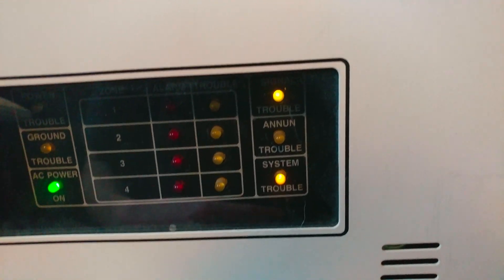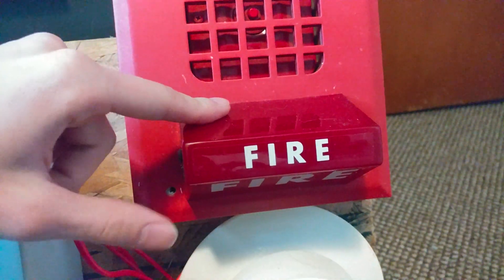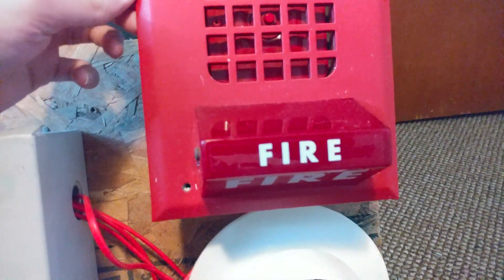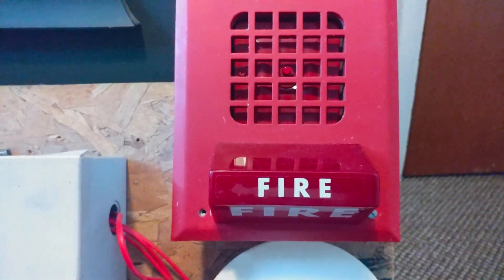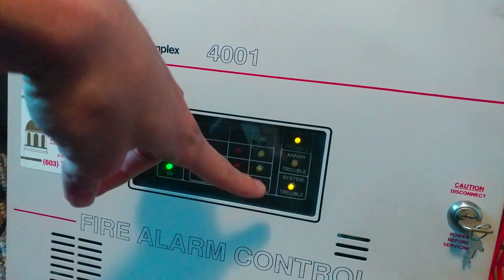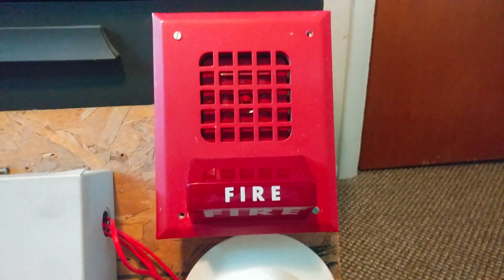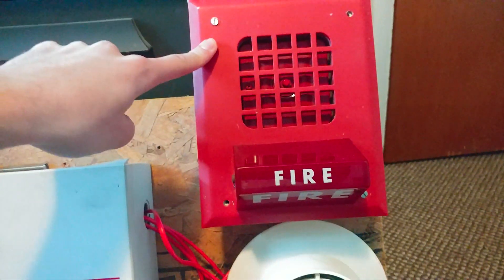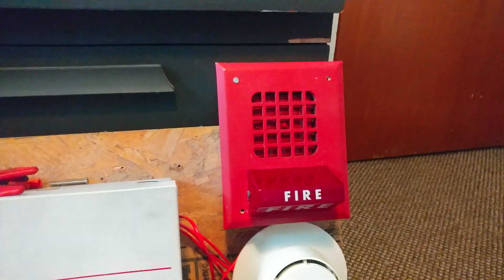As far as the signal trouble I mentioned at the beginning of the video — the reason there is a signal trouble is because the light on this thing apparently has no polarization diode. It still works, I did test it out, it just doesn't have a diode on it. Even though there is an end-of-line resistor, there's just no polarization diode, so that's why there's system trouble. But that's pretty much your view of this device — pretty cool. I'm really lucky to have one of these; I've never seen these in buildings before.